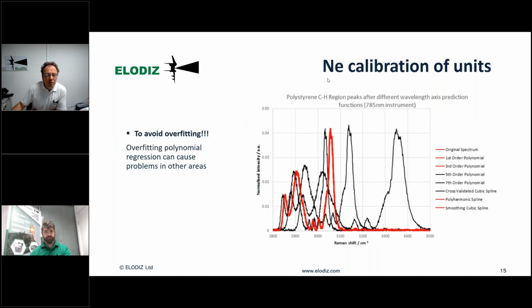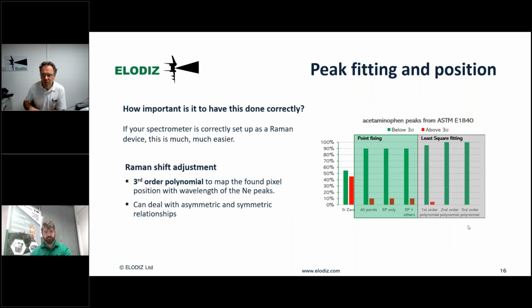So what happens if we don't do this correctly? What happens is that people just take the neon maximum and then try to extrapolate it somehow. The problem is that we have observed in some of the instruments in the consortium, in which we have approximately 25 instruments that we have analyzed, that if you overfit some of the data, then you have problems in the data reproducibility, particularly observable on the CH area of the instruments that we have been using. So peak fitting is quite important, but then as well peak adjustment.